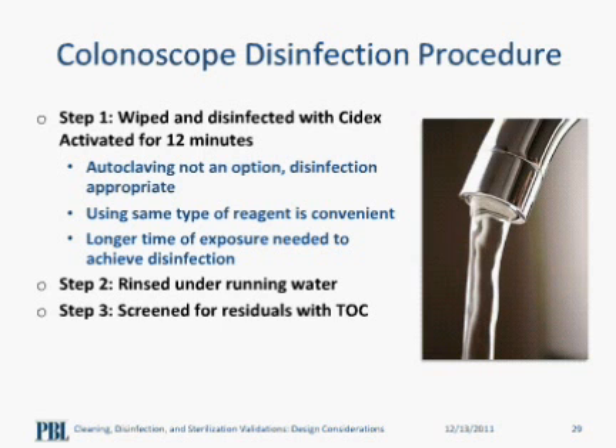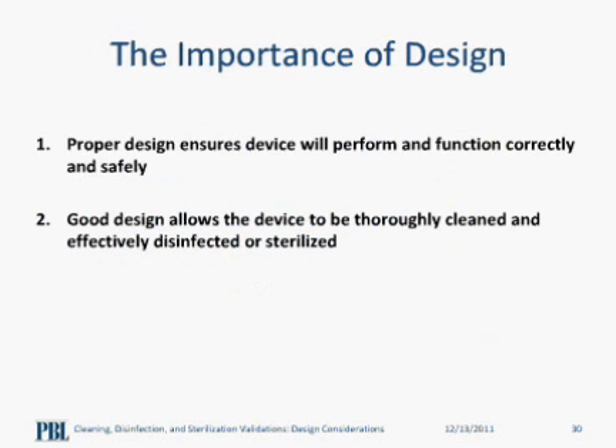I will move on to the next slides, which are about device design and what design factors are important to assure the efficacy of the cleaning and disinfection or sterilization processes. Why is design important in manufacturing reusable medical devices? Design is the most important aspect in manufacturing reusable medical devices because a medical device intended for reuse must be properly designed to ensure that it will perform safely and effectively throughout its useful life.